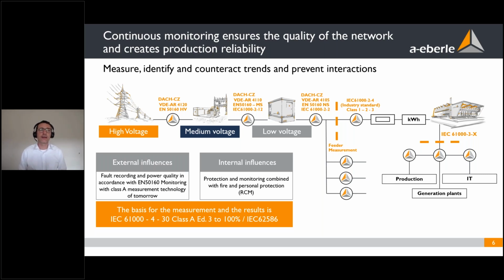So under which environmental circumstances the product has to be stable enough to calculate all these measures. For example, a PQ meter from our side must handle high EMC environments. Clear, because we want to measure in substations and local grid transformer stations, for example, where there is a high EMC field, and the worst thing is that we are influenced by others, for example by temperature. In the IEC 62586 standard, it is exactly described how to manage that inside our measurement technology, to provide reliability for the measures which we are calculating.